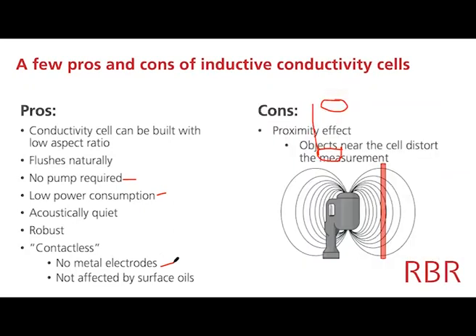I think probably the main downside, and the thing that we're going to discuss in the next little bit, is that the measurement of conductivity is, let's put it this way, the signal that the conductivity cell measures is highly sensitive to what's happening inside the cell. So in a sense, the bulk of the measurement is happening inside here, but the cell can pick up changes in conductivity out here, which means that anything in the field of the cell can distort the measurement. And that would be one of the things that we need to address here.